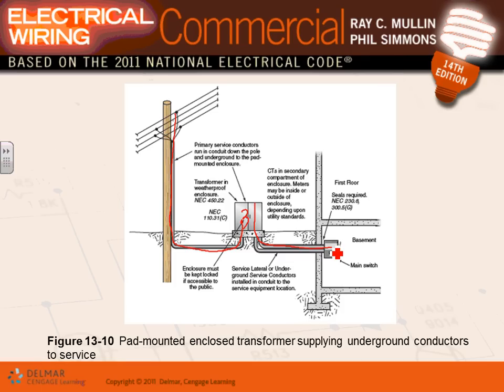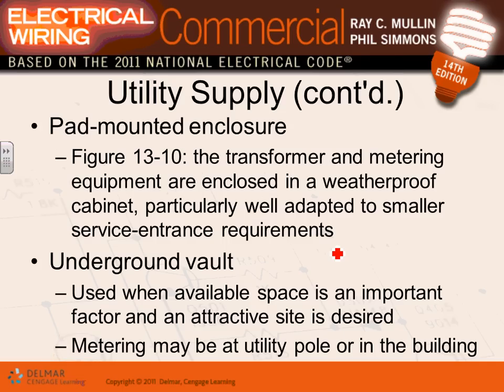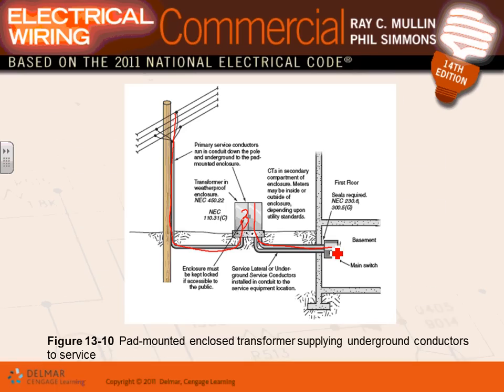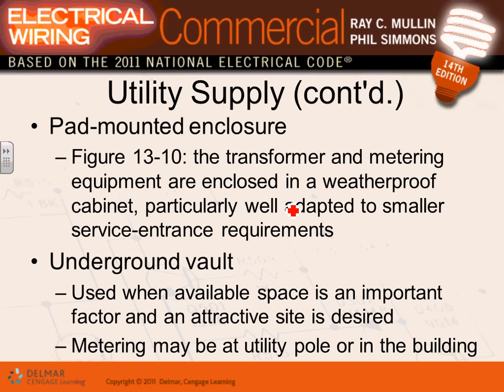Can you guys see that? We came from the top into a beautifully tamper resistant box sitting outside underground. Everything is hidden. Everything's underground down to the disconnect. That's the most preferred one. When you have a pad mounted transformer, guys, they can have the CTs sitting somewhere here, and sometimes they have a meter here. So the metering section that you did, Adam, we have a CT cabinet, we call it, CT cabinet metering section, either part of the transformer or another box sitting next to the transformer. Why do we have the CT cabinet, guys? In order to meter the power coming to us.